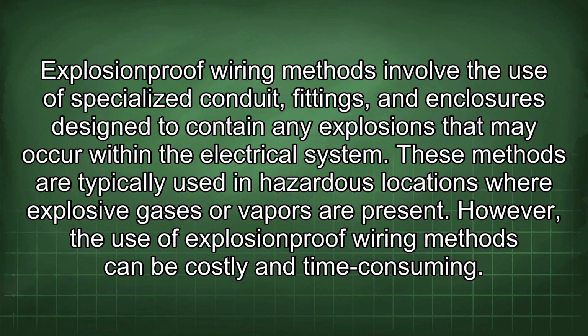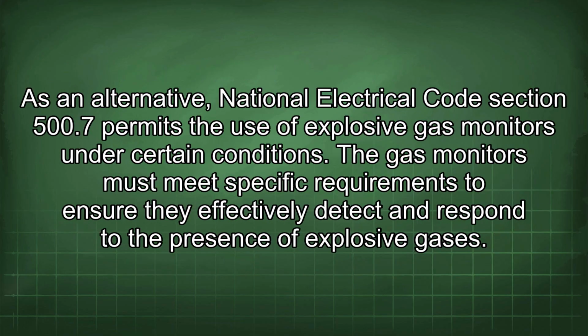Explosion-proof wiring methods involve the use of specialized conduit, fittings, and enclosures designed to contain any explosions that may occur within the electrical system. These methods are typically used in hazardous locations where explosive gases or vapors are present. However, the use of explosion-proof wiring methods can be costly and time-consuming. As an alternative, National Electrical Code Section 500.7 permits the use of explosive gas monitors under certain conditions.